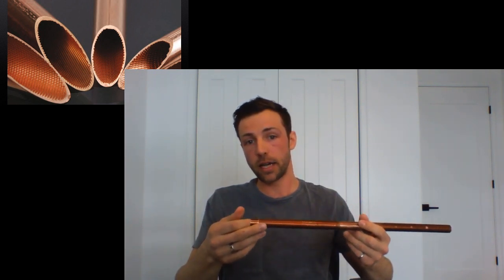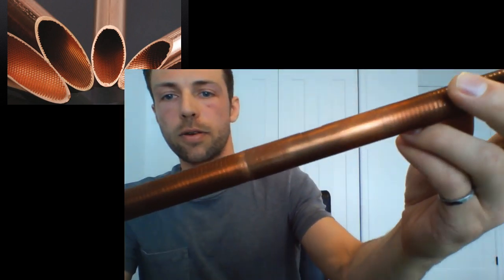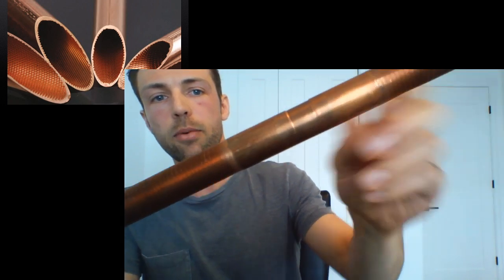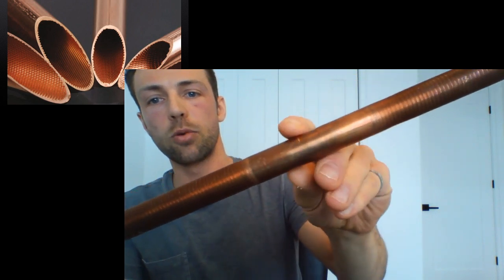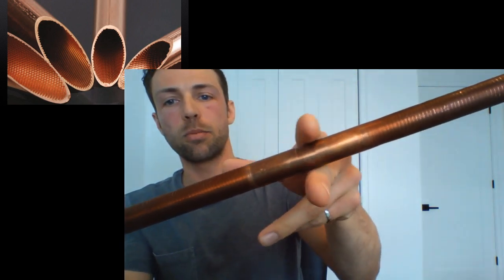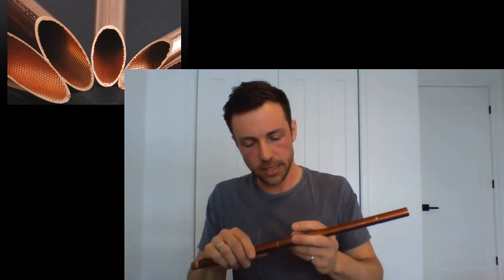The most commonly found defects are ID pitting, small holes and pits inside the tubes, and OD fretting at the land area. Here we have an example of OD fretting, which is a loss of material you can see at the land area, coming from the support plate vibrating in this region and removing material. There are also ID cracks and ID corrosion.